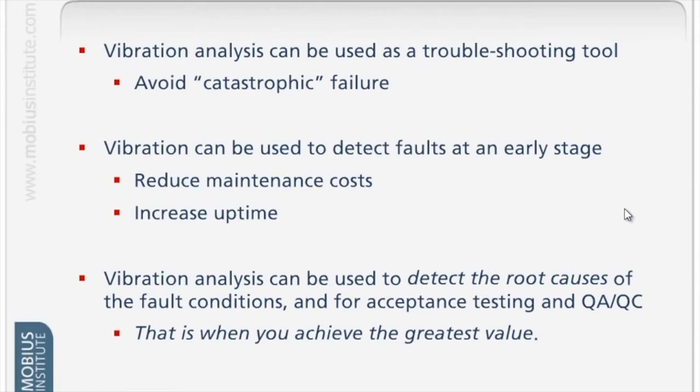Let's be proactive. Let's put a force field around the plant and use vibration analysis for acceptance testing. Let's test that pump and the motor and the fan as it comes into the plant, in agreement with the vendor. And we tell the vendor, if it doesn't pass our vibration test, we're not accepting it. Now you might think, why would you do that? Of course the brand new pump or the recently rewound motor, they're going to be in great condition, aren't they? Not always.